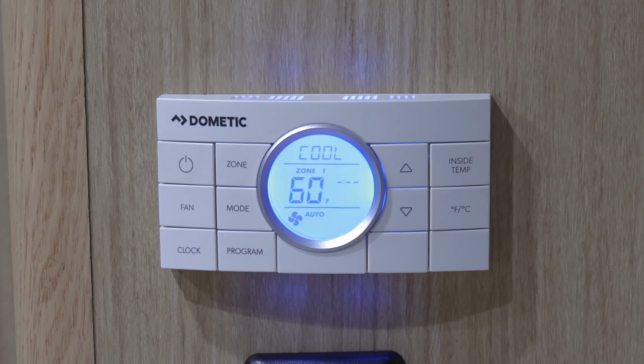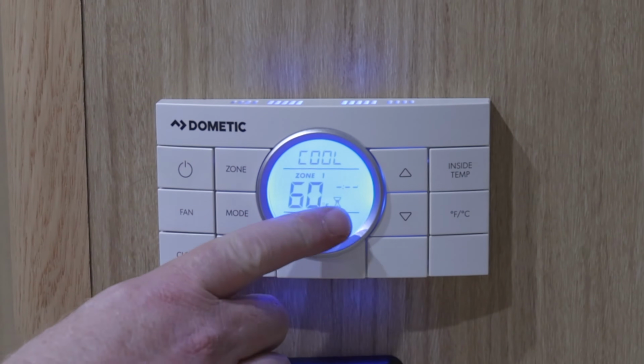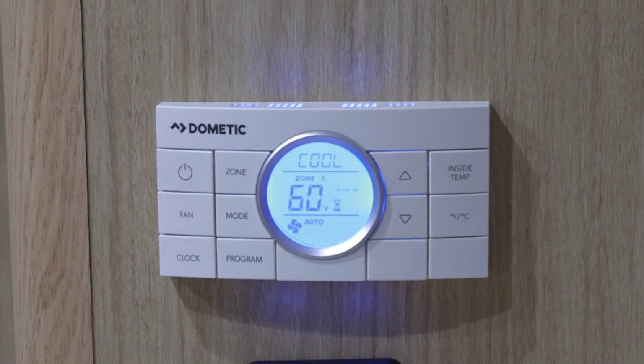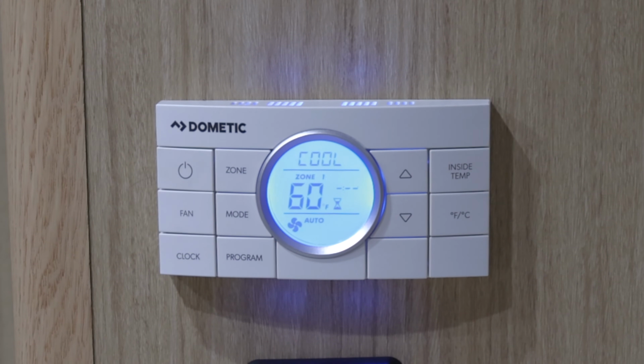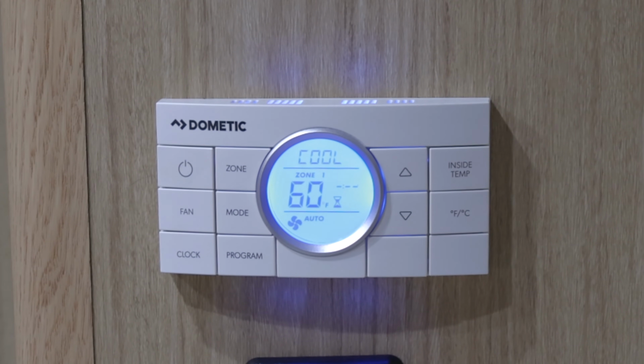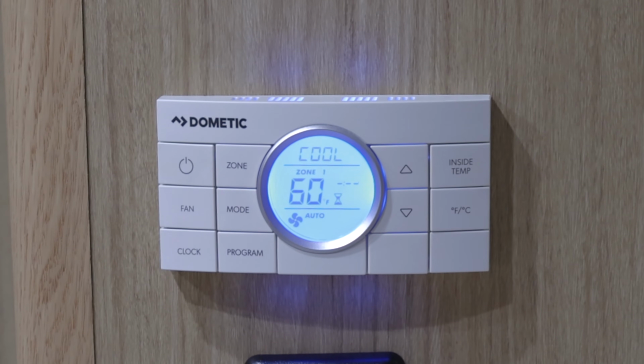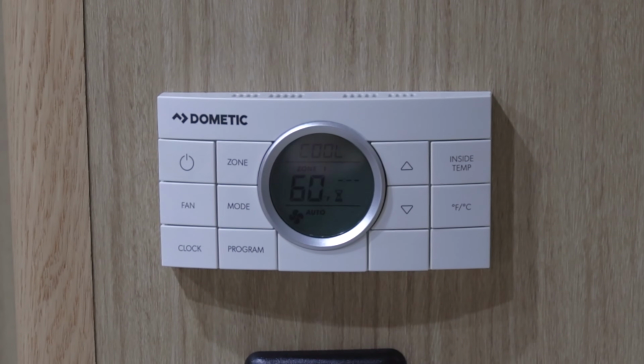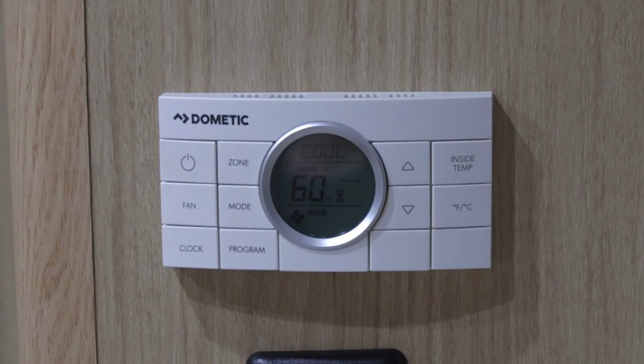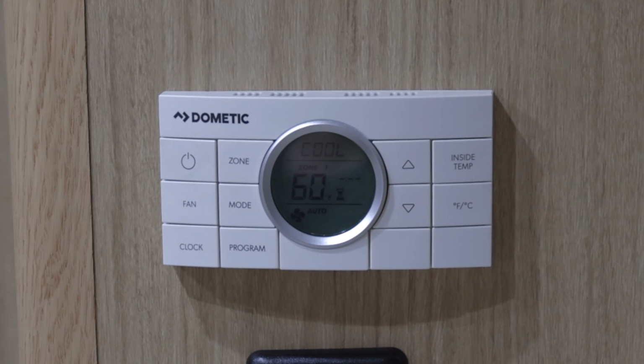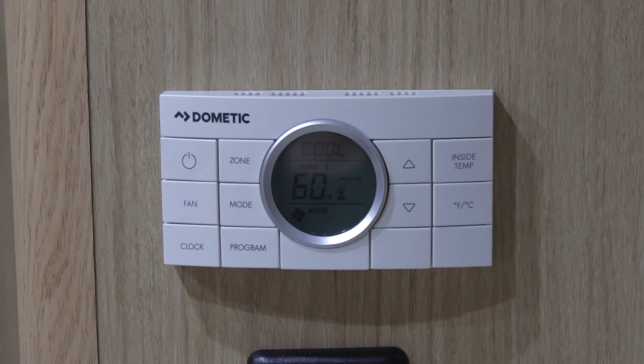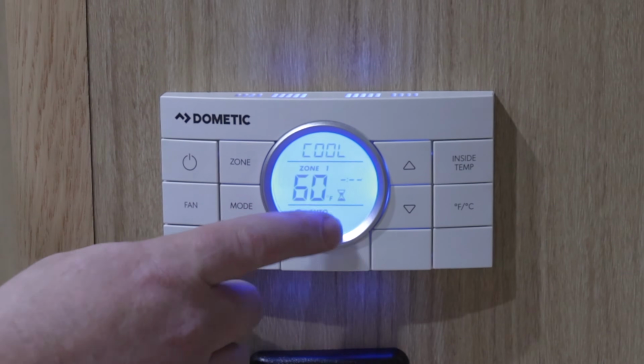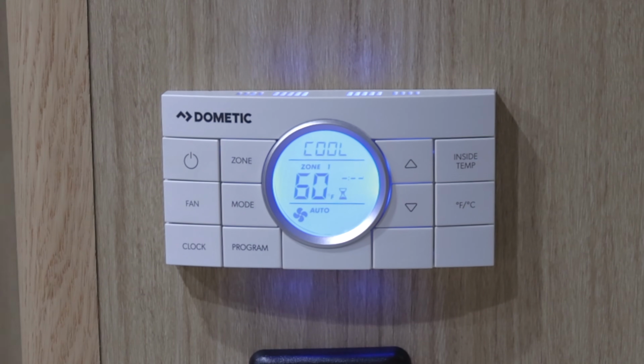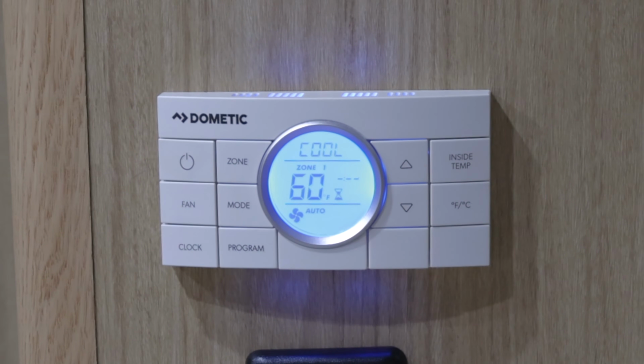Be aware they do not fire up immediately. Typically, we'll see a little hourglass pop up. The fan will come on after a few moments, and then the compressor kicks in about 30 seconds after that, and that's when you'll see that hourglass disappear. So we're going to wait for this. All right, there we've got the fan coming on, but you'll note we've still got the hourglass on the screen. We're still waiting for that compressor to kick in. And there we have the compressor kicking in.